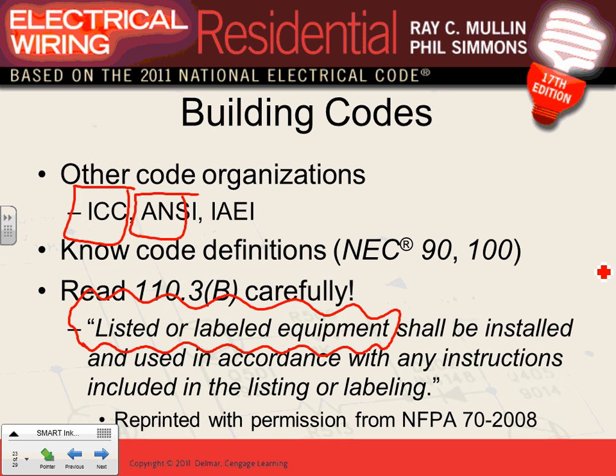For example, this fixture is listed and labeled as an indoor fixture. Can I put it outdoor? No. So that's basically what listing and labeling means - you have to install them following the manufacturer's instructions, based on their listing and labeling, which says indoor, outdoor, and so forth.